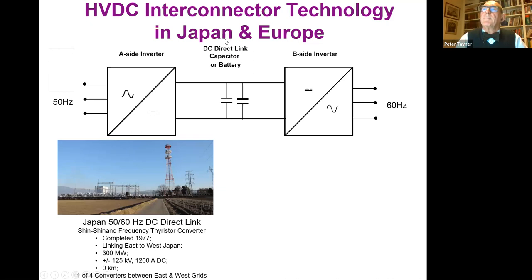So in Japan, there are four of these converter stations between 50 hertz and 60 hertz. Here's one, frequency thyristor converter, completed in 1977. It's 300 megawatts. The DC link between the two is plus and minus 125 kV, so it's 250,000 volts across, and it's passing up to 1200 amps DC. So it's handling 300 megawatts, and there are four of these converter stations.